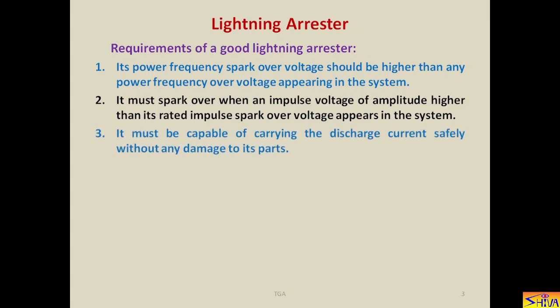Third, it must be capable of carrying the discharge current safely without any damage to its parts. So when the lightning arrestor sparks over, the current flows through the lightning arrestor, that is also impulsive in nature. This current is called the discharge current. So the lightning arrestor is tested for discharge current also, and there are two different ratings for this discharge current. One is the discharge current and second is the maximum value of discharge current.